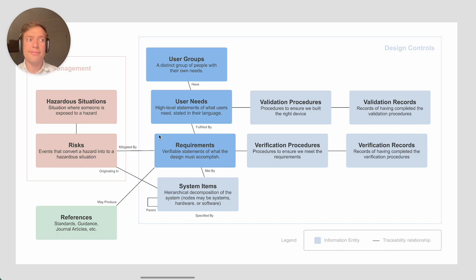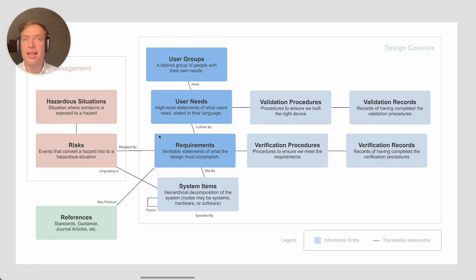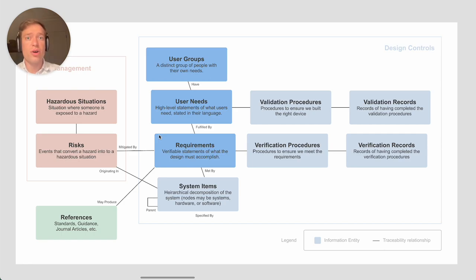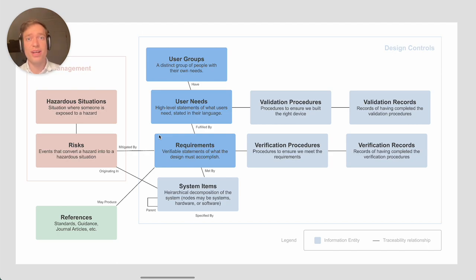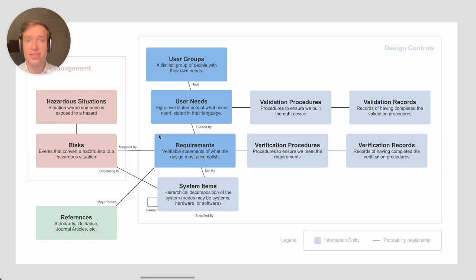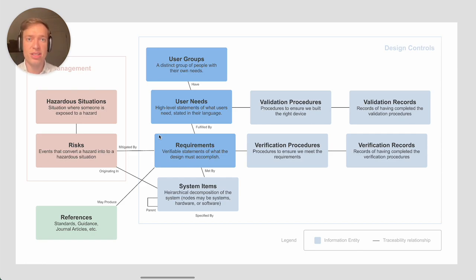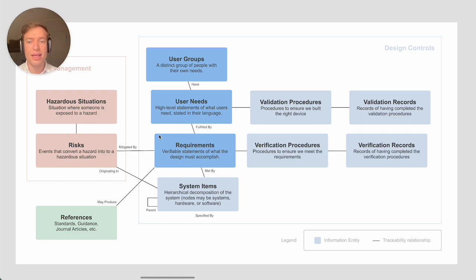Maybe you have a user need that says colorblind users can use the device, and the requirement is there's no information that's communicated using only color. That could be verified by inspecting every user interface component, every report, and saying is there some way a colorblind person could get the same information that's represented in the color.